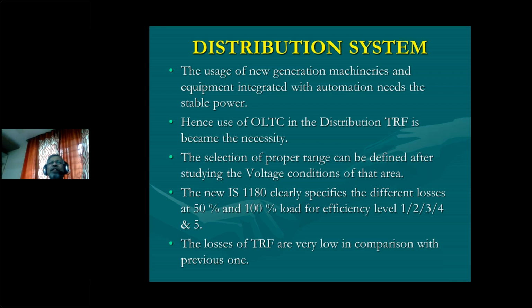The selection of proper range: in normal OLTC you can have 9 taps or even 17 step positions. It can be 1.25% or 2.5%. There are a lot of concepts for the selection of it, but widely you have to consider the current situation of that area and select the proper range. The normal range you can consider is a total of 20%. It can be minus 10 plus 10, or minus 7.5 plus 12.5, or plus 7.5 minus 12.5, depending upon your location. Now let us move to new standards of the transformer.